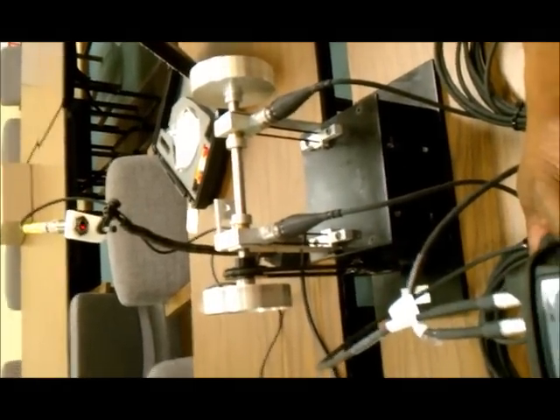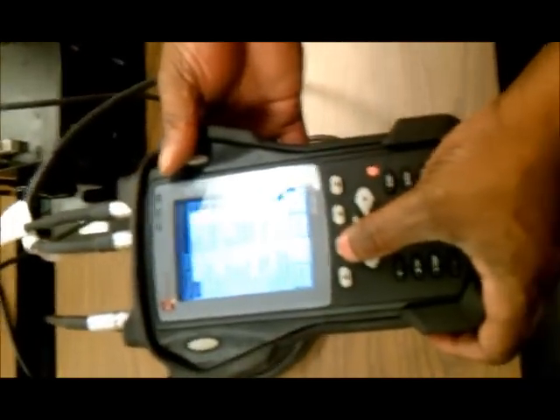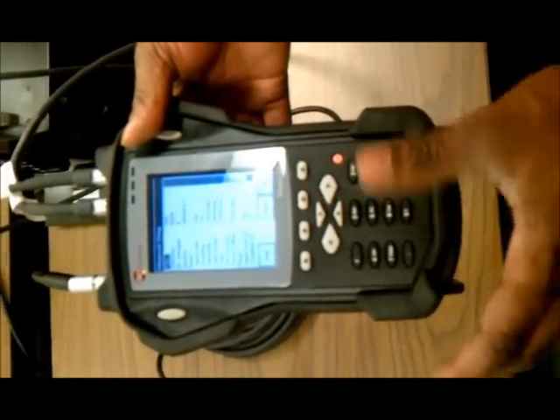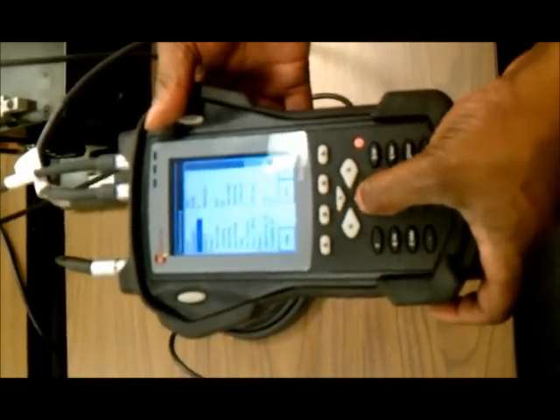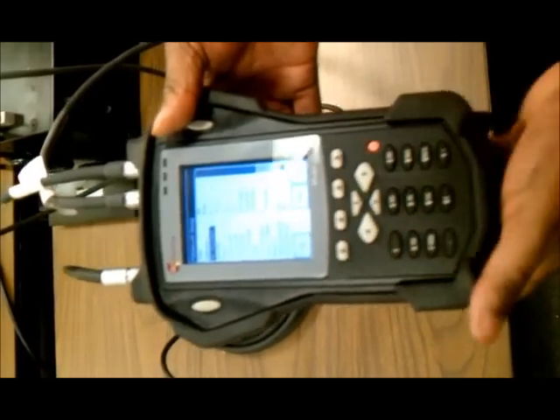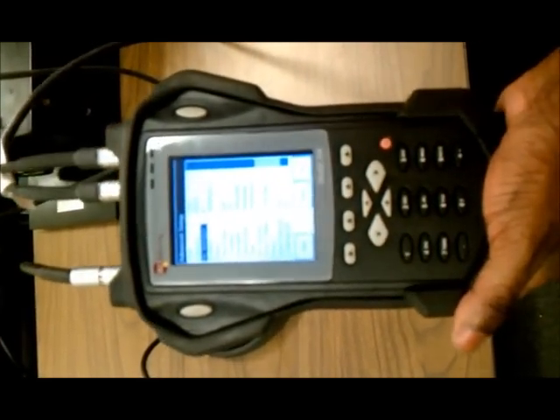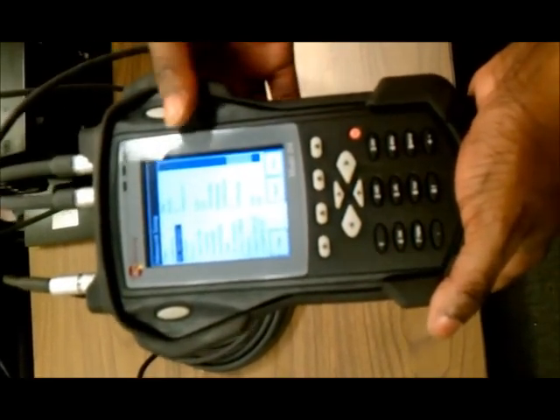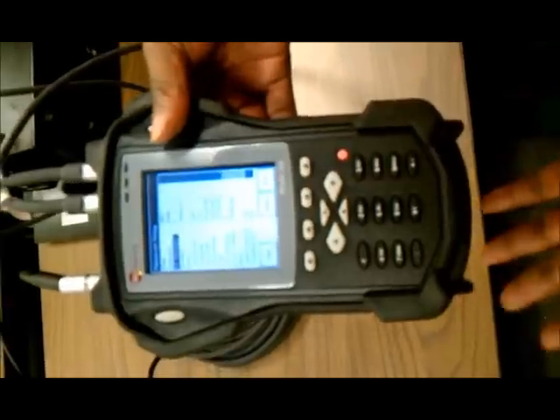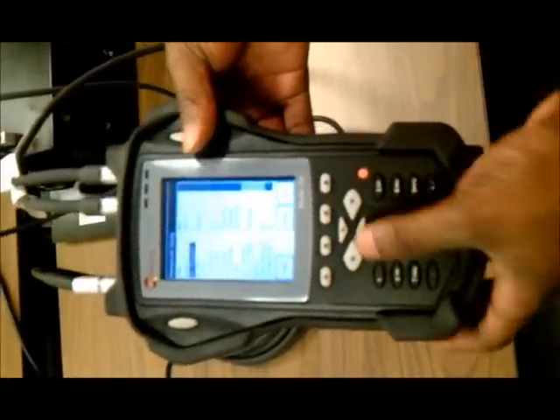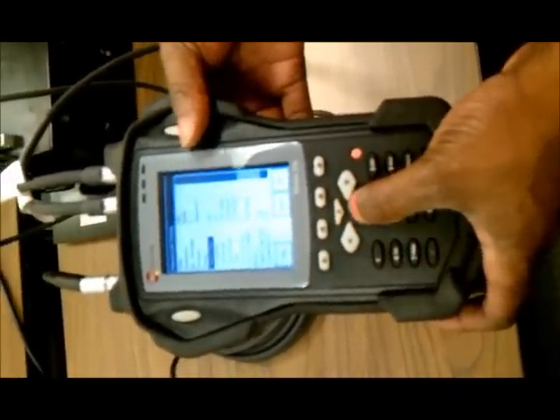So what we'll do now is hit options, which will allow us to set up the rest of it. For our detection, we want peak to peak, so we get the whole forward and back motion. Our solution is going to be influence coefficients because we're using the trial weight method. And what we'll do now is set up our planes.